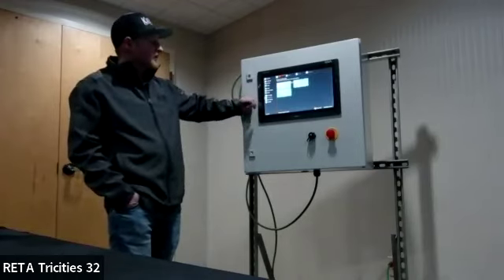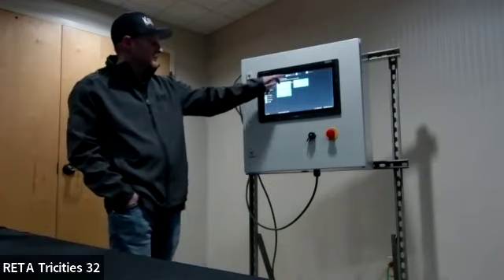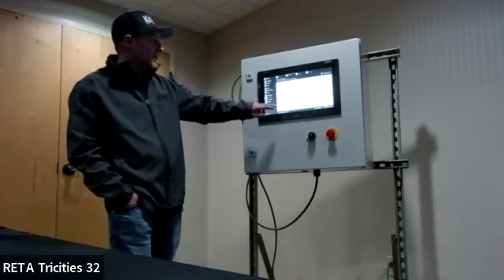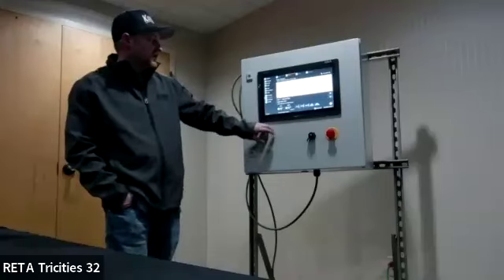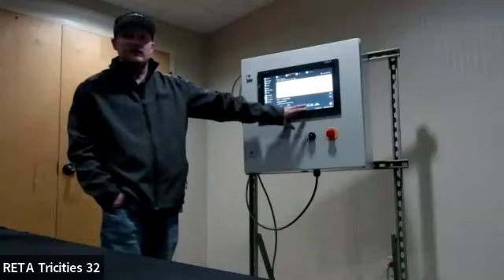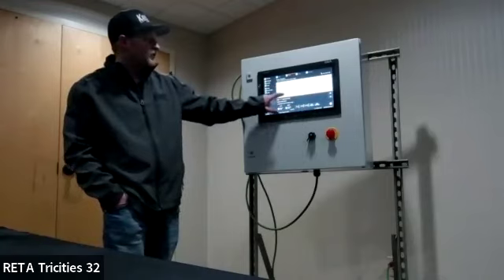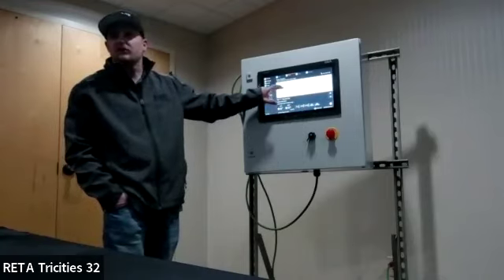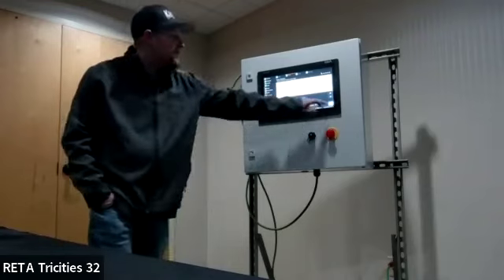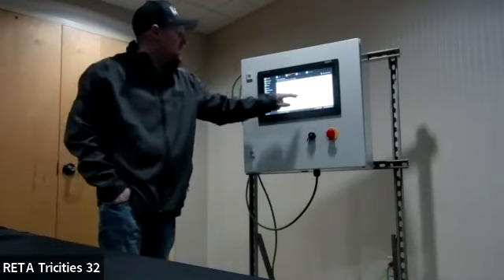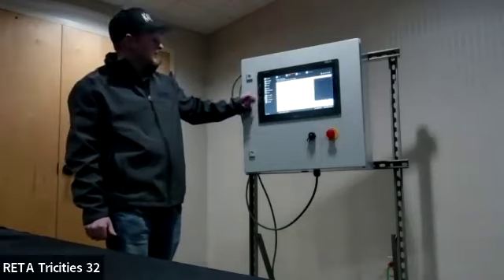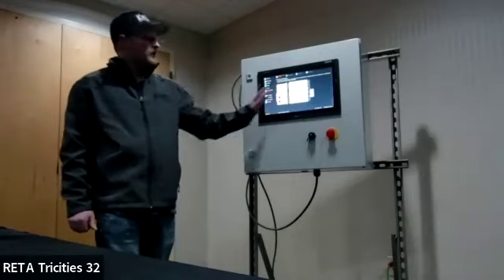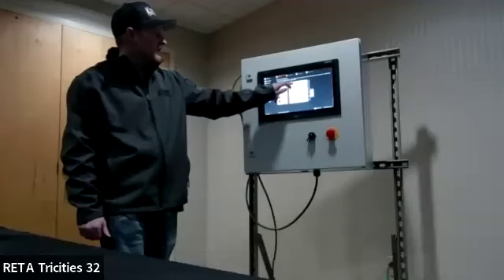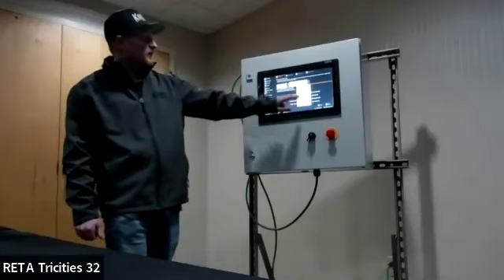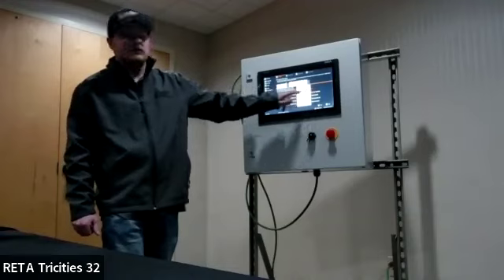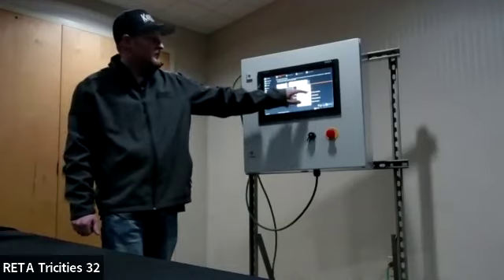It's actually, you can go to configuration here, sensors, and just go like you're going to calibrate the slide valve. Okay, so then you can turn the oil pump on right here, and you can load it, unload it, and you can also scroll through here and see your pressures. Copy. Another way to do it, to run the oil pump, is to come in here to service, where it's gonna show your slices, okay? And you come in here to digital output, click on that, and you're gonna have oil pump motor start, so you can click that to manual.